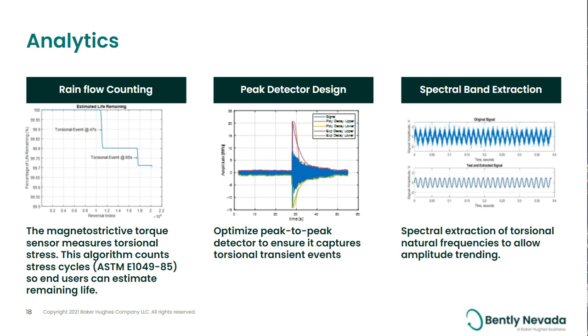In the plot on the left, shaft life starts out at 100% and remains at this level as the machine operates, until the machine experiences a transient event with amplitude levels high enough to exceed the endurance limits of the shaft. Once the machine returns to steady state operation, the remaining life estimate again is constant. At the next transient event, there is another reduction in shaft life. In this way, it is possible to trend and monitor remaining life of a component.